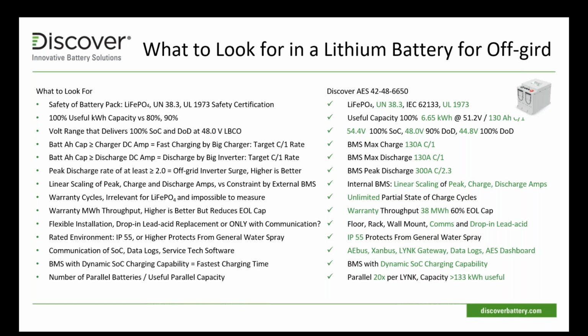Another thing that is very confusing with lithium batteries out there are the warranty cycles that are put on a lot of the data sheets. Typically, this is really irrelevant information for lithium ion and really impossible to measure if you look at the warranty support documents. There is no way to measure cycles in many of the lithium-ion batteries that are promoted out there. We have no restriction on partial state of charge. Again, our warranty supports throughput of energy. So throughput is the amount of energy put in charging and the amount of energy discharging added up. And we have a performance warranty of 38 megawatt-hours throughput. Our digital BMS will log this information for you, and we can get it out of that, and it can be communicated. Really, that's what some of the communication systems are all about.